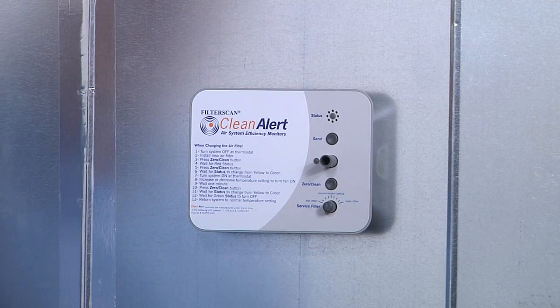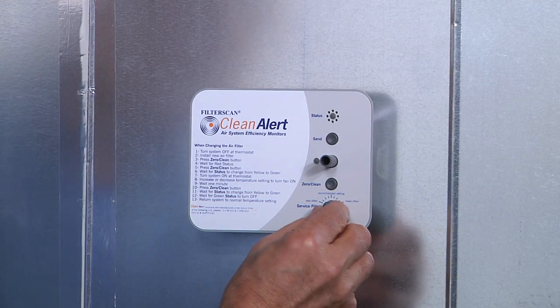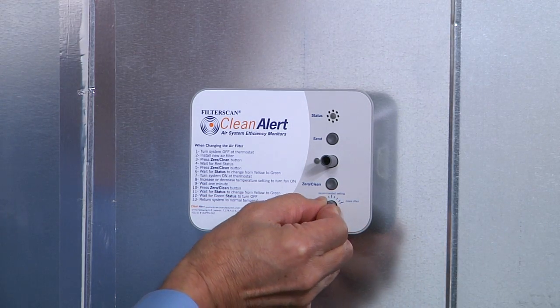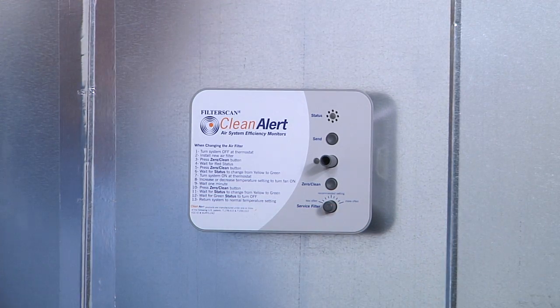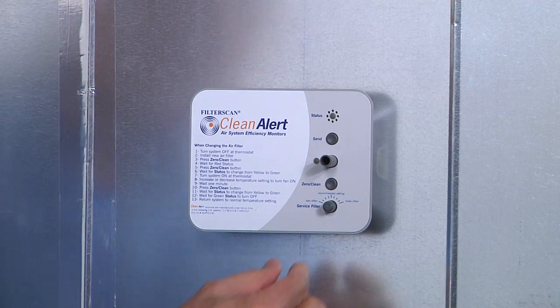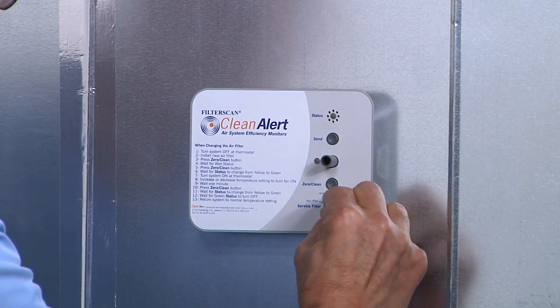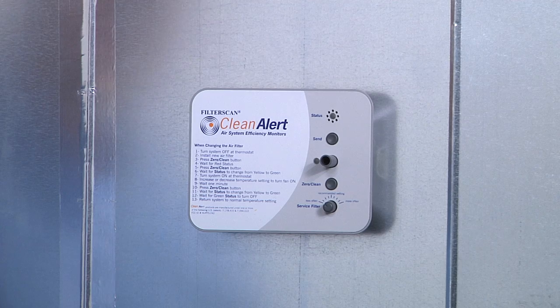The service filter control is a fine-tuning adjustment that has been calibrated to the mid-range recommended setting at the factory. This control allows the user to change the point at which the clog alarm will be triggered. Turning the service filter adjustment clockwise will cause the Filterscan to issue an alarm at a lower level of filter clogging. Turning the service filter adjustment counterclockwise will cause the Filterscan to issue an alarm at a higher level of filter clogging.